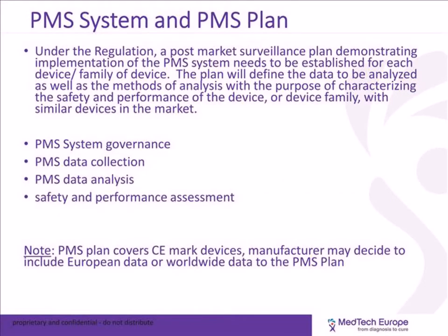One of the most important requirements of this new regulation in the post-market arena is a requirement to establish a post-market surveillance plan for each device or each family of devices. So this plan should define the data which are to be analyzed, and it needs to be established for each family, for each device or similar device which are on the market.